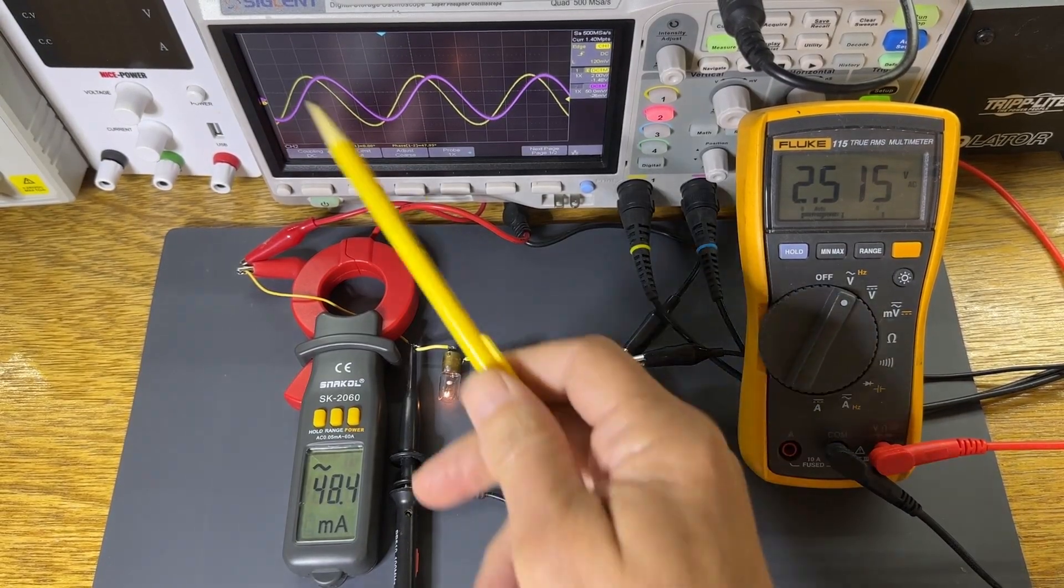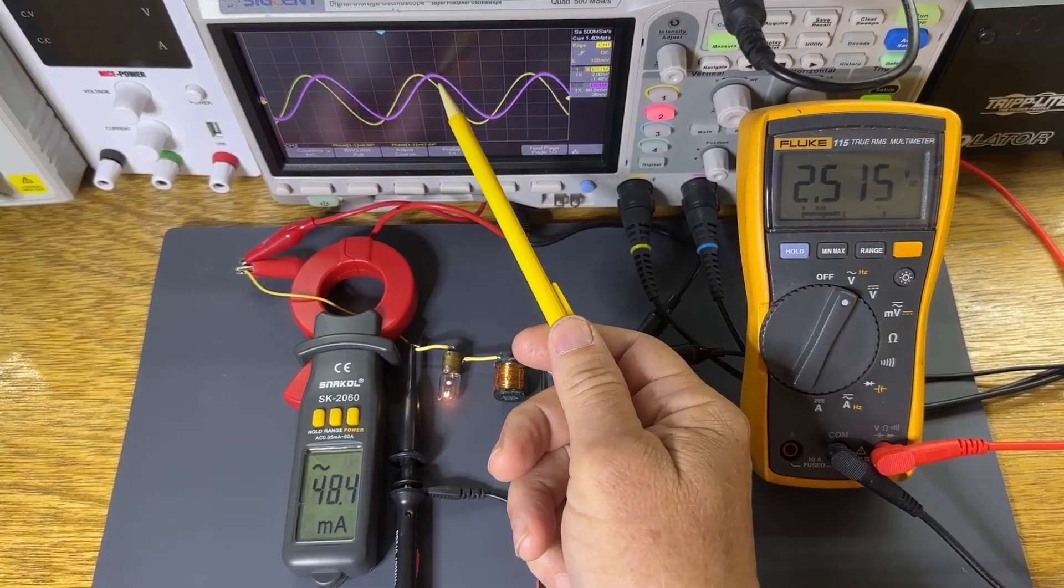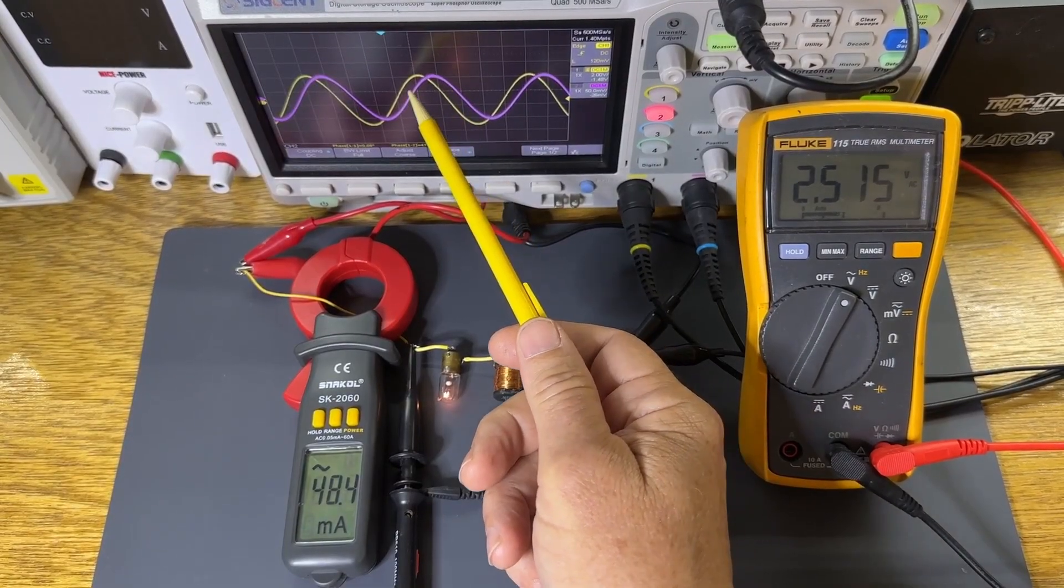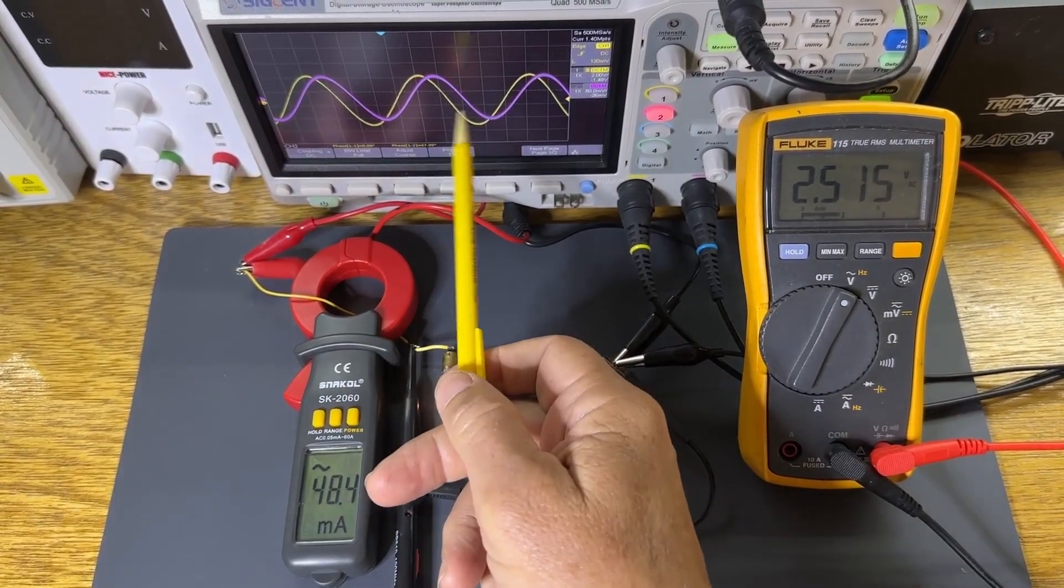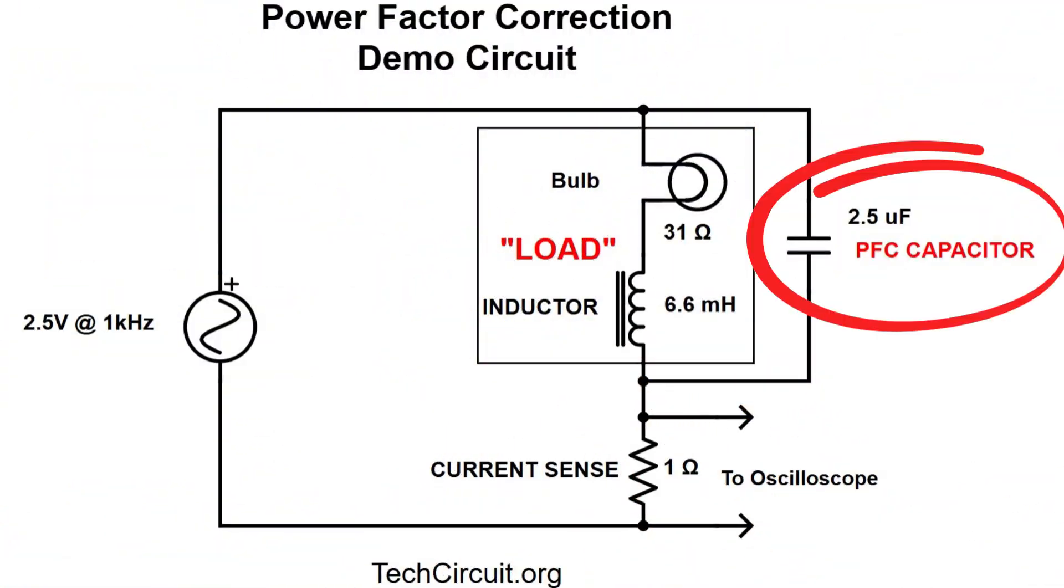That's the capacitor we'll connect across the load to neutralize that lagging reactive current and bring the power factor up to nearly 1.0. So we'll put that value capacitor in parallel with the load as shown in this schematic.